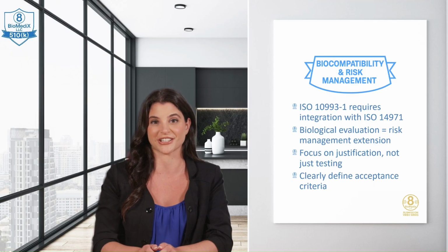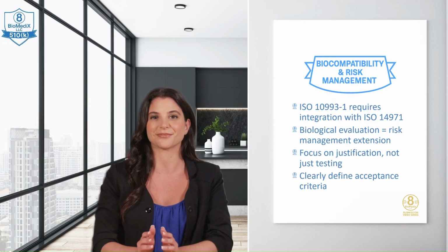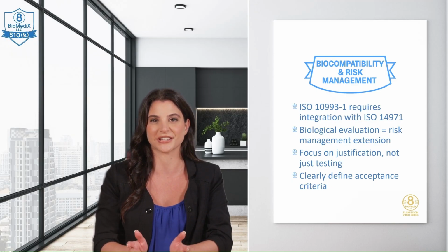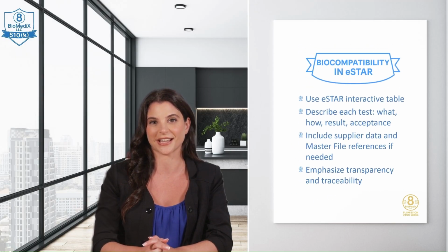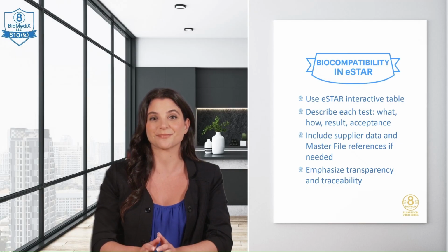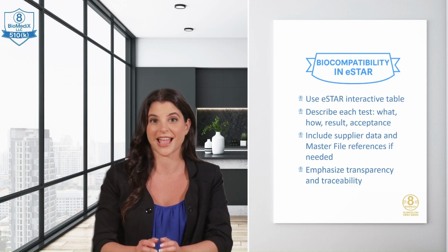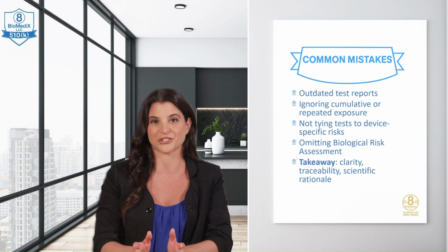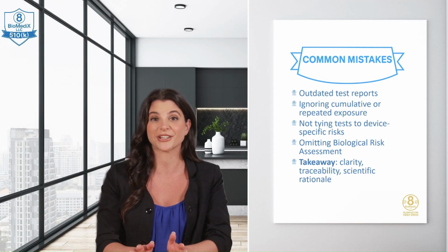What acceptance criteria are you using? Inside eSTAR, you'll use an interactive table to summarize each test. For each one, explain what was tested, how it was tested, the results, and why they meet your acceptance criteria. If you reference supplier data or master files, eSTAR includes fields to list them and provide access details. The key here is transparency. Show your test rationale, show your risk linkage, and show your logic.